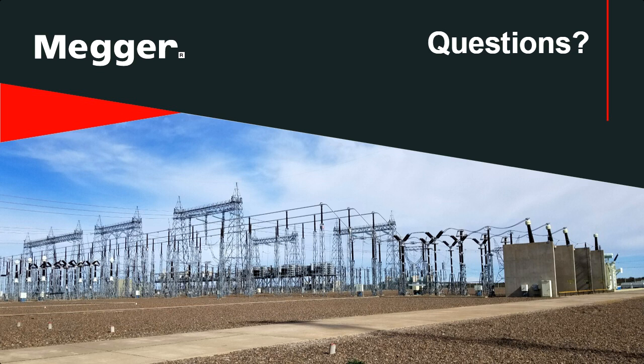What is a minimum voltage check? So the minimum voltage check is the amount of voltage that the breaker is going to operate at, based on the control voltage for the coils. Like the close and trip coils run off of DC, usually on the UPS battery system out of the control house. And they have a range that may vary a little bit, but most of the time it's listed as between 70 and 140 volts DC. So your minimum voltage check is making sure what's the minimum voltage that the breaker is still going to operate at.